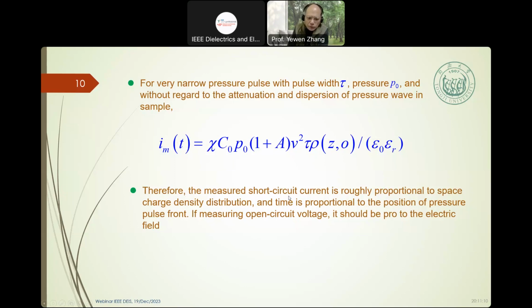Therefore, the measured short circuit current is roughly proportional to the space charge distribution, and the time is proportional to the position of the pressure pulse front. If measuring in open circuit, it will be proportional to the electrical field. So if we measure current, voltage...